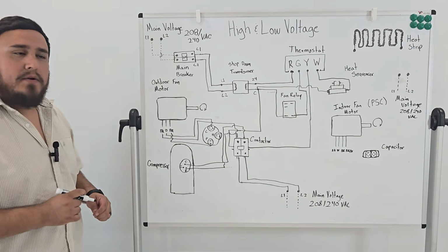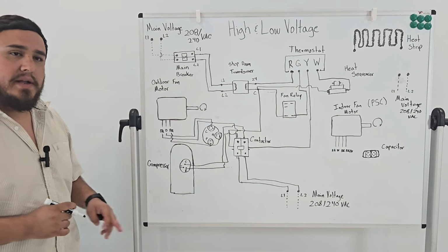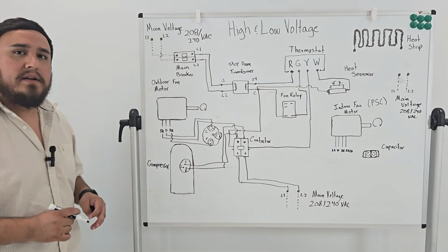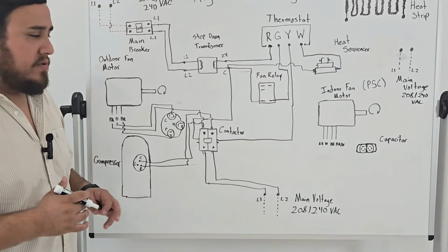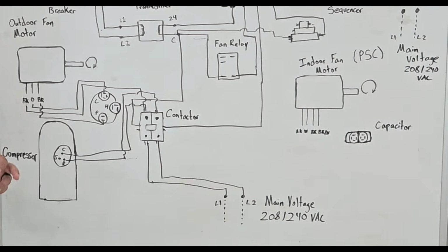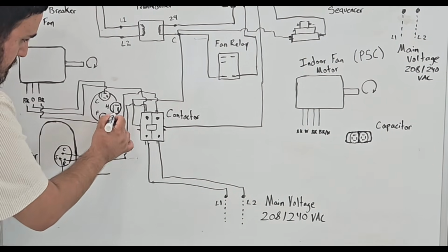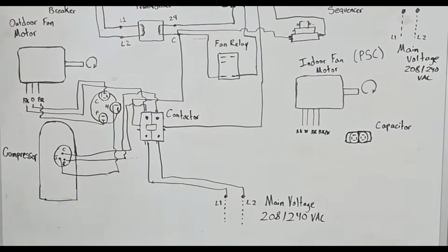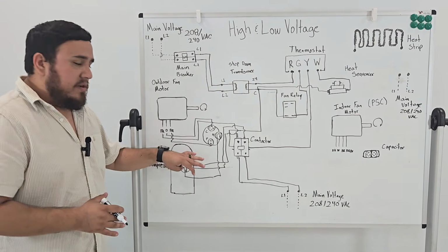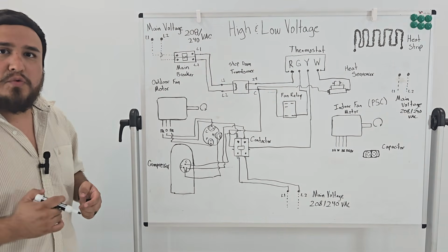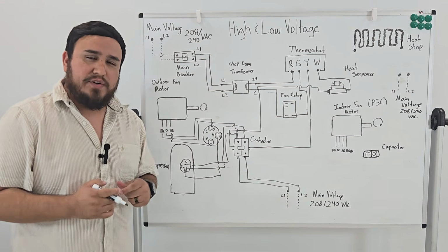All right, so now the only one that's missing to be connected is the start winding for the compressor. That one is going to go to the hermetic, or H, or in this case, they'll say Herm on your capacitor. Now we have successfully connected my compressor, but we're still missing a wire. I don't know if you all got it or picked it up.